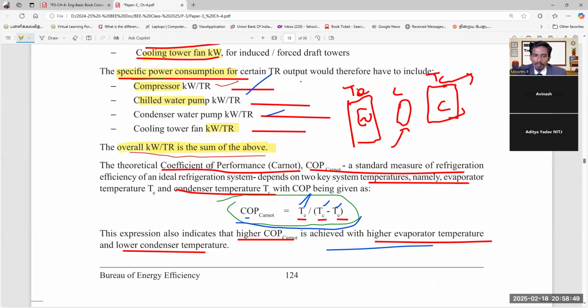Another one is the coefficient of performance of the refrigeration system, very important, two formulas available. COP - very important, they always ask this for 1 mark. This is the Carnot cycle, this is a standard measure, using only the temperature. The refrigeration system depends on two key temperatures: one is the evaporator temperature. The condenser temperature is also measured. Using these temperatures, they measure the COP.